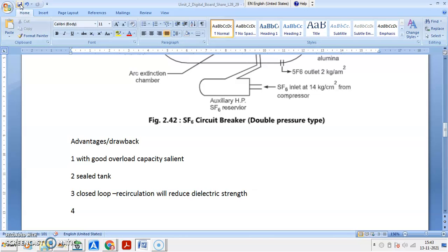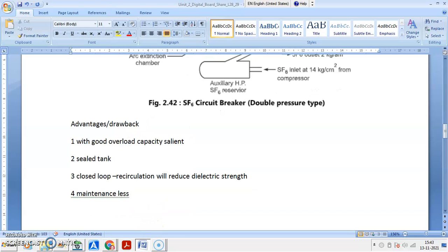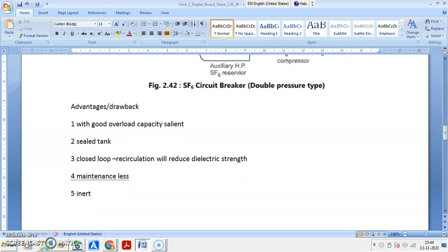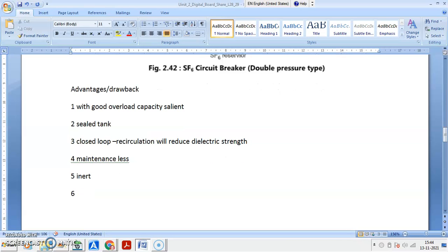Then with SF6 gas, you know that maintenance is minimum compared to air and oil circuit breakers. Less maintenance is there. Of course, there are some advantages, some disadvantages. Poor voltage problem, contact corrosion, because of the inert property which we have. The inert property is good for SF6 gas. So less over voltage problem, less corrosion of contacts. That is also an advantage. So you may not be required to replace the contacts frequently.